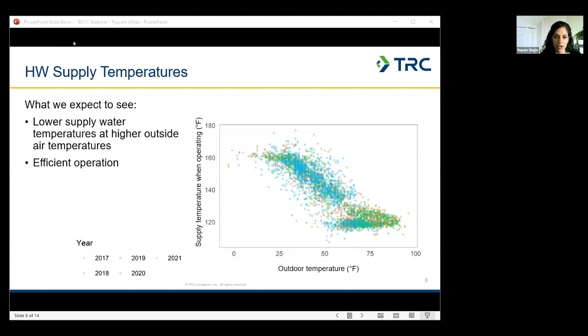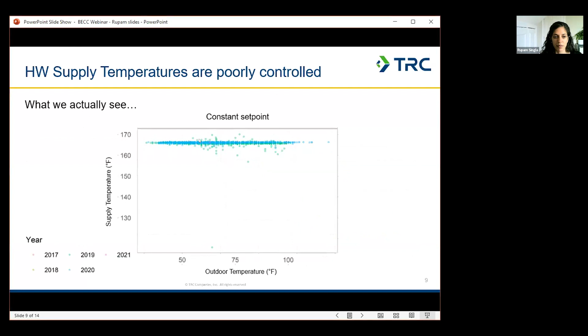This was something that we saw quite a bit, where it was just a constant set point. So this is actually 5 years worth of data. And you can see here that across all the outside air temperatures, across all the 5 years, that supply water temperature is around 170 the entire time.